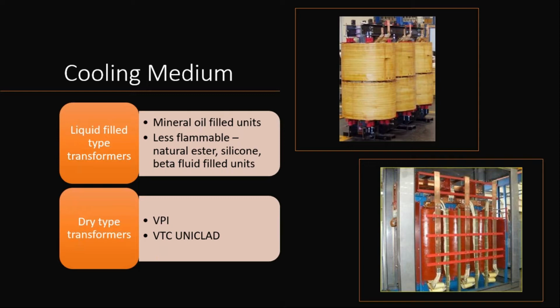When we go to dry types, there are two types of construction which VTC makes. One is VPI, which uses varnish and vacuum pressure impregnation. The second is totally encapsulated coils, which is VTC's brand name Uniclad. In this, all coils are completely encapsulated, which protects from dust and other humid environment conditions. The third one is cast coil, which we are not in the business of, but it is similar to Uniclad and has a higher chance of partial discharges. That's the reason our business limits us to Uniclad. So those are the few constructions we could do.